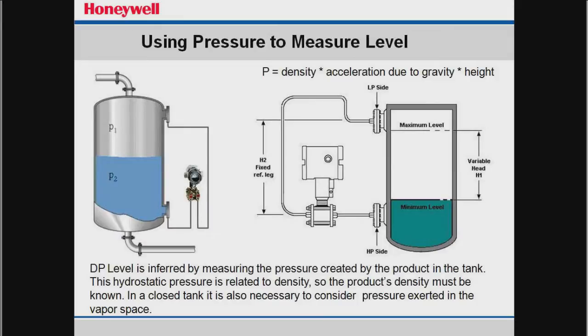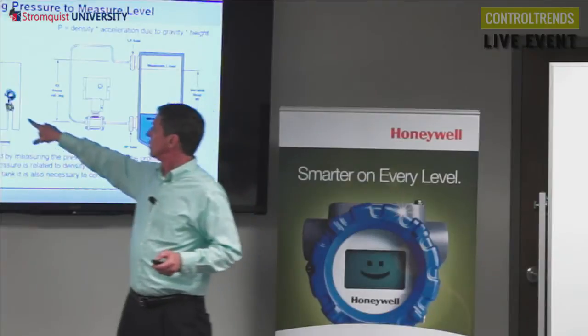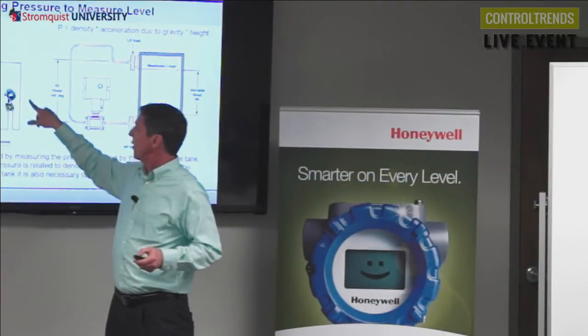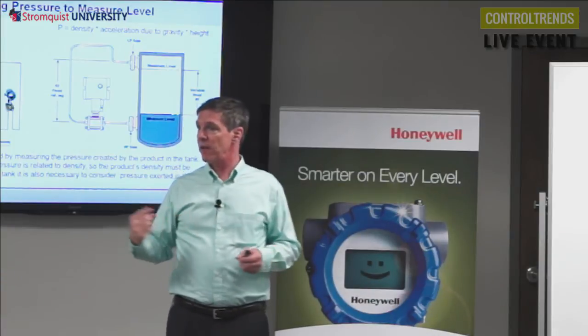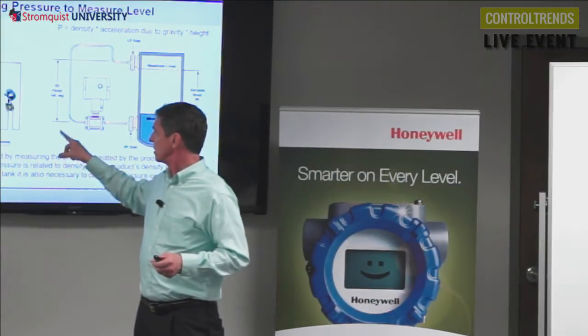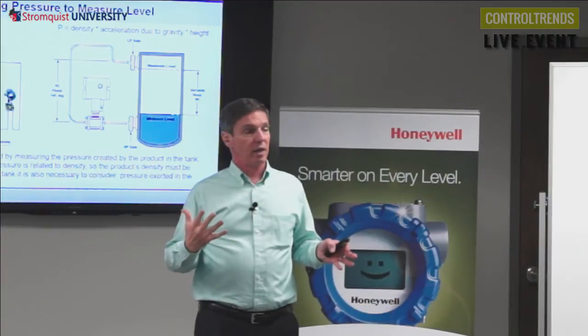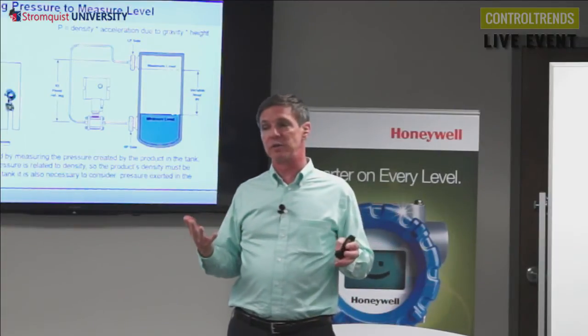Okay, the next one is using pressure to measure level. In this case, we're using differential pressure. If you look over here, we're showing a differential pressure transmitter. One side is connected to the bottom of the tank, the other side is connected to the top, and this is using impulse lines, so we're measuring the pressure directly. And it really just works off this idea of hydrostatic pressure.